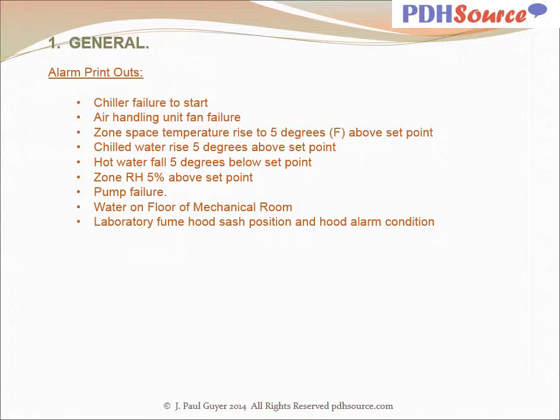Alarm printouts: chiller failure to start, air handling unit fan failure, zone space temperature rise to 5 degrees above set point, chilled water rise 5 degrees above set point, hot water fall 5 degrees below set point, zone relative humidity 5% above set point, pump failure, water on floor of mechanical room, laboratory fume hood sash position, and hood alarm condition where fume hoods are installed.